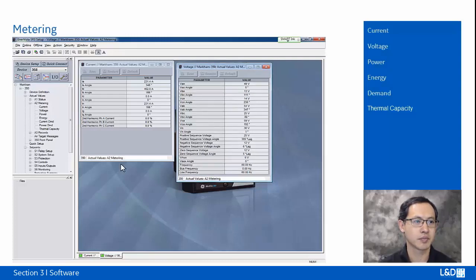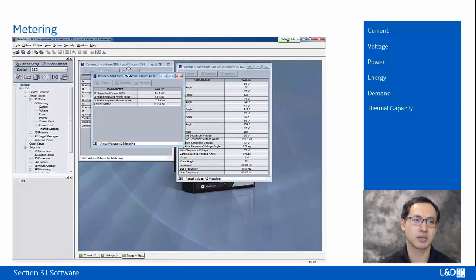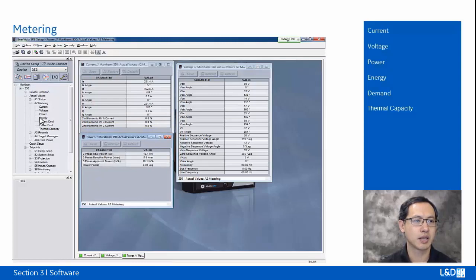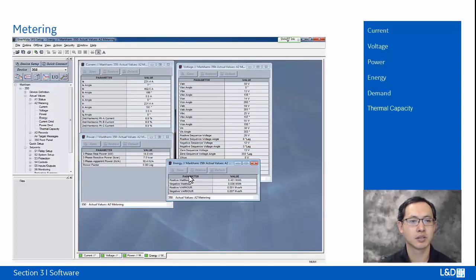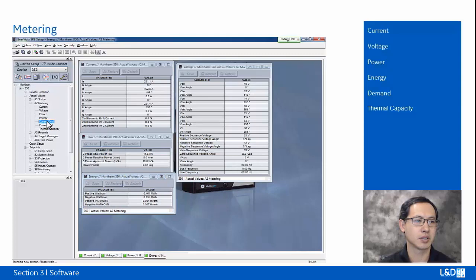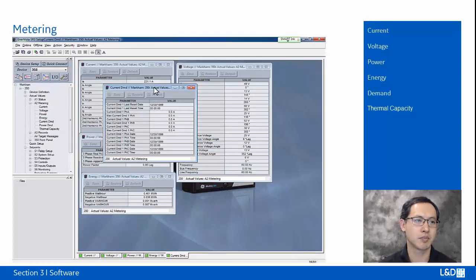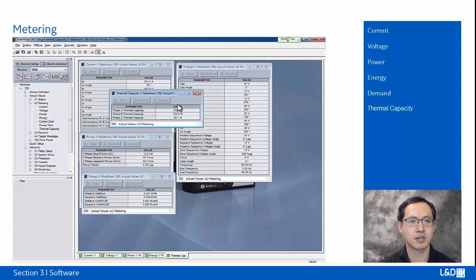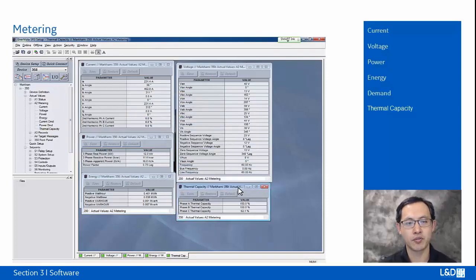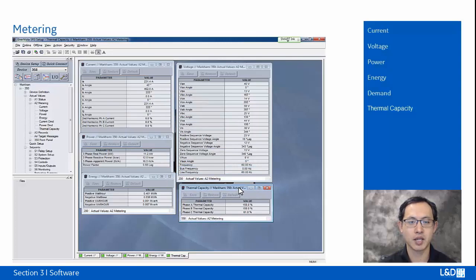And other metered values we can see are the power, energy, and also the current demand and voltage demand. And for the thermal capacity, this is only for the 350 relay's cable thermal capacity, and later we will come to the 339 motor relay, which has a different thermal capacity display.